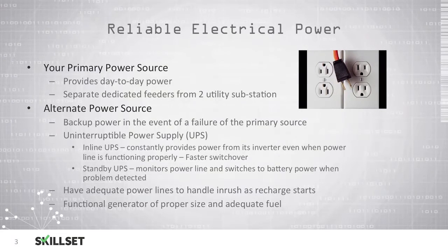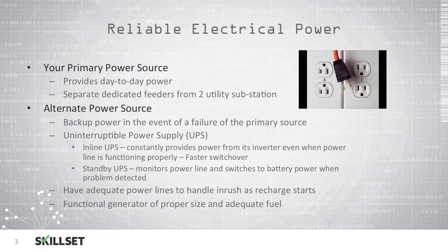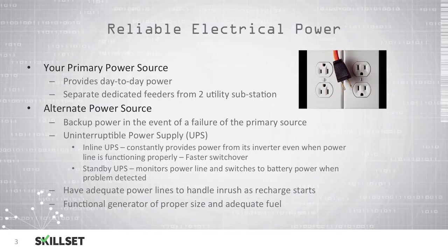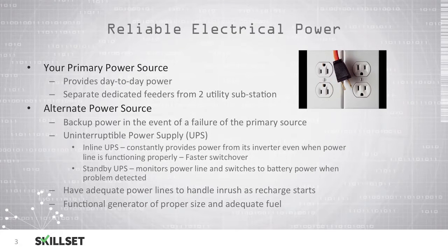You also should make sure that you have an alternate power source in case the primary source fails. One way of doing this is by using an uninterruptible power supply, or UPS. There are two types of UPSs. Inline UPSs are constantly providing power from their inverters even when you have utility power, and can switch over to battery faster if the power goes out than a standby UPS. A standby UPS monitors the power line and switches over to battery when a problem is detected. However, these systems could have a small delay which could cause your machines to reboot, so an inline UPS is considered to be better, although it will also be more expensive.